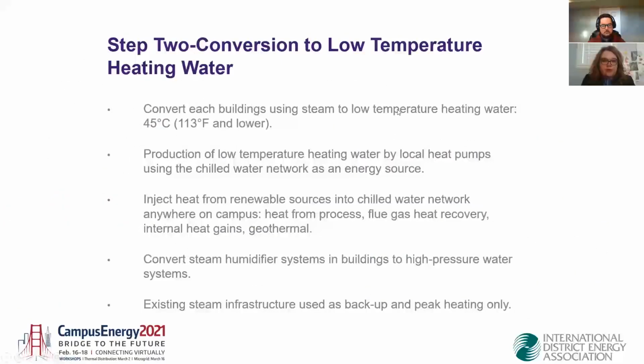So step 2 was the conversion to low temperature heating water by adding heat pumps in buildings. The purpose is to convert each building that's using steam to low temperature heating water, which is about 45 degrees C. So we're not exceeding that supply temperature, just to maximize the efficiency of our heat pump. Of course, there are networks that are using higher temperature water, so those networks are kept as is, but usually we're able to convert maybe 60 to 70% of the heating demand to low temperature water.